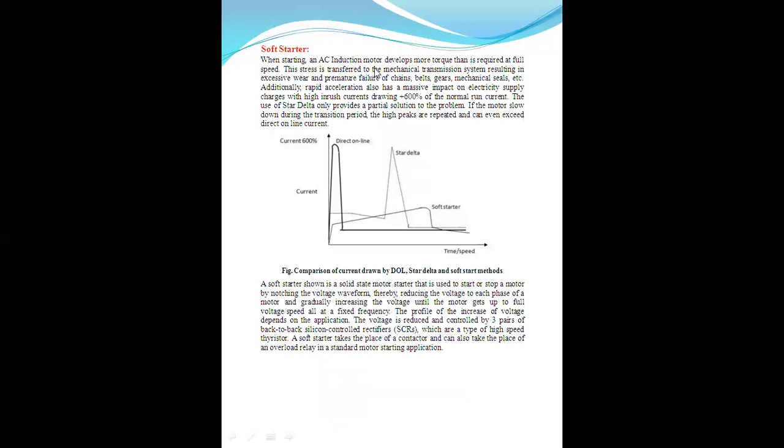When starting, an AC induction motor develops more torque than is required at full load speed, and the stress is transferred to the mechanical transmission system, resulting in excessive wear and failure of chains, belts, gears, mechanical seals, etc. Additionally, rapid acceleration also has a massive impact on the electricity supply, with high inrush current drawing plus 600% of the normal run current.